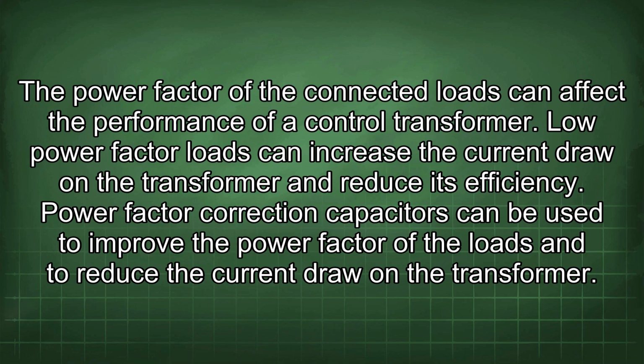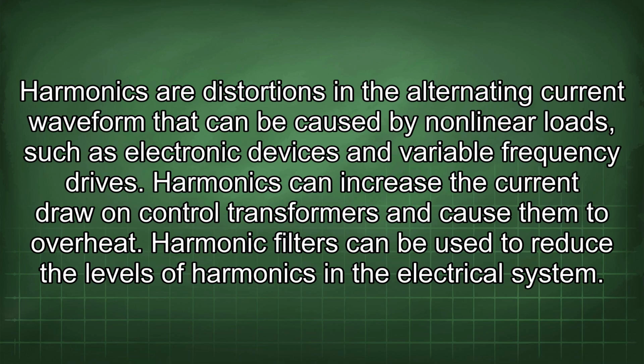Harmonics are distortions in the alternating current waveform that can be caused by nonlinear loads such as electronic devices and variable frequency drives. Harmonics can increase the current draw on control transformers and cause them to overheat. Harmonic filters can be used to reduce the levels of harmonics in the electrical system.